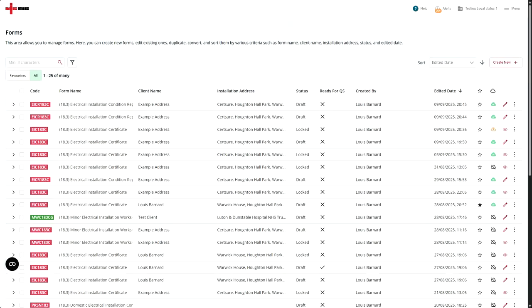We've had a few questions around the intelligence of the system. If I pick on one of them, it was, does the web software now identify failed measured values to those of maximum permitted with regards to maximum ZS? I don't believe it does, but you might correct me if it does. That's a great feature which we might look to provide enhancements to in the future. So if your measured ZS value that you record is greater than the maximum permitted ZS for the protective device, then it would be great to flag it.